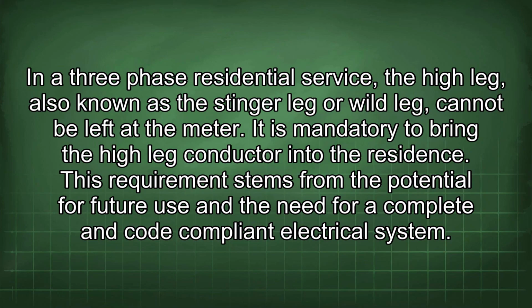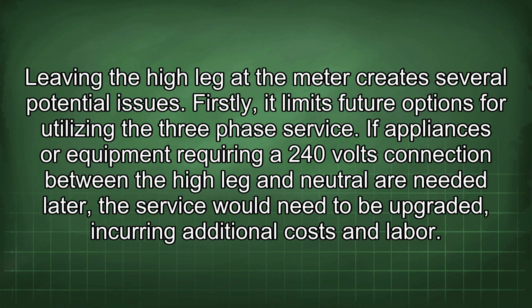In a three-phase residential service, the high leg, also known as the stinger leg or wild leg, cannot be left at the meter. It is mandatory to bring the high leg conductor into the residence. This requirement stems from the potential for future use and the need for a complete and code-compliant electrical system. Leaving the high leg at the meter creates several potential issues.